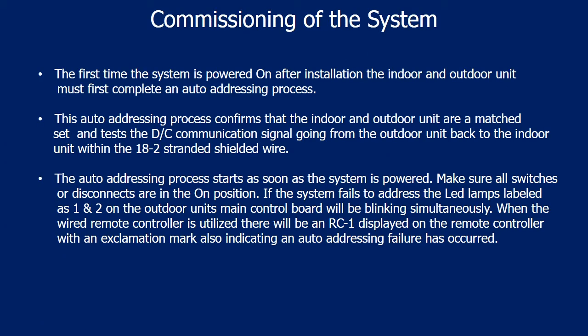The first time the system is powered on after installation, the indoor and outdoor unit must first complete an auto-addressing process. This auto-addressing process confirms that the indoor and outdoor unit are a match set and tests the DC communication signal going from the outdoor unit back to the indoor unit within the 18-2 stranded shielded wire. The auto-addressing process starts as soon as the system is powered. Make sure all switches or disconnects are in the on position.